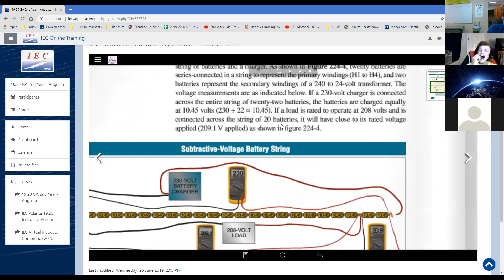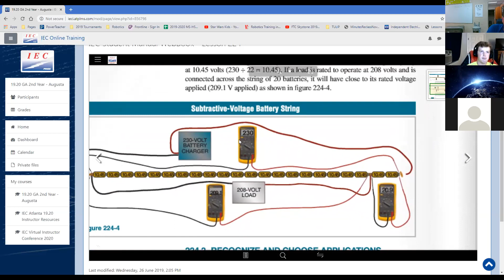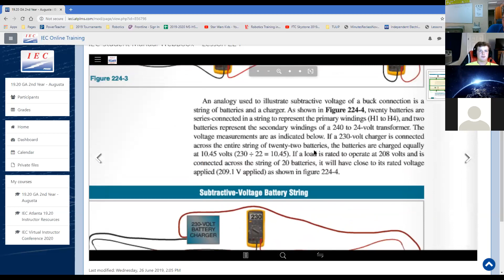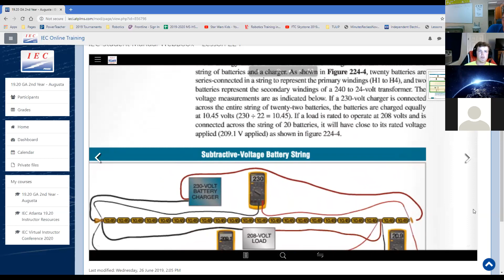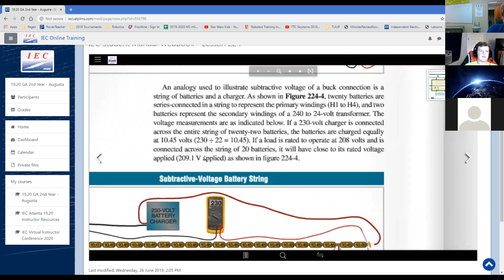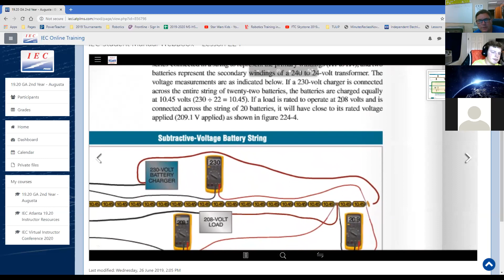But on the same token, if you put a battery charger on here, you would only get a portion of that, 230 divided by 22, because it's 22 batteries. That's all the batteries, right? 10.45 volts total. If the load is rated to operate at 208 and connect a string of batteries to 20, it will have close to the rated voltage of 209. 208 to 209 is not a big deal. So.